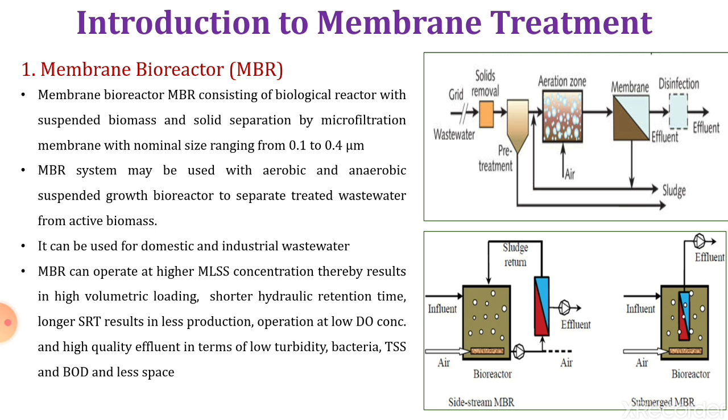Next is the technology, the membrane treatments. Now let us see what exactly is the membrane treatment, what is the membrane bioreactor and all. Membrane bioreactor, MBR, consists of a biological reactor with a suspended biomass and solid separation by a microfiltration membrane with nominal size ranging from 0.1 to 0.4 micrometer.